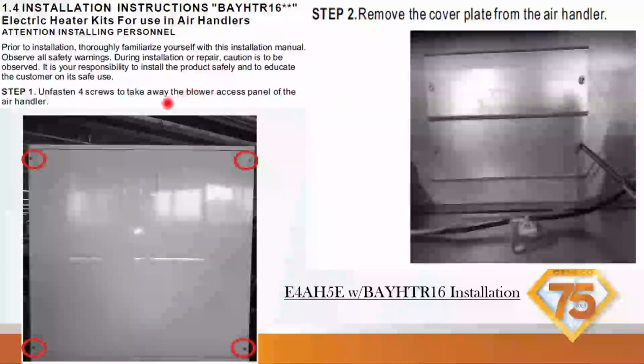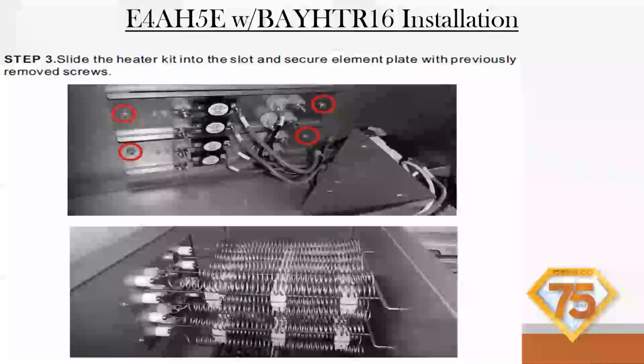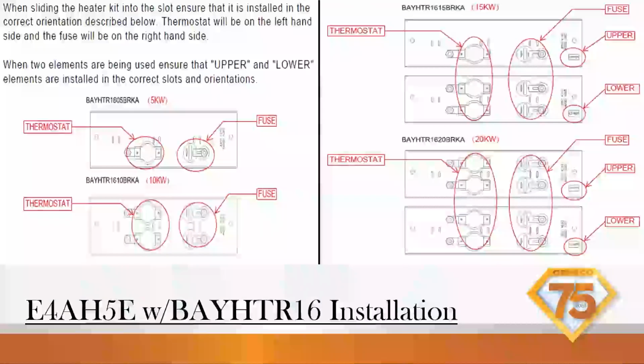Unfasten the 4 screws. Take away the blower access panel of the air handler. So remove the door panel. As you can see, this is a 20 kW. So we have an upper and a bottom, and they are going to have these labels. Slide the heater kit into the slot and secure it with the previously removed screws. You guys are probably used to those. You're going to have to line those up. They do line up pretty good sometimes. Well, most of the time. I have had a few heat strips where they didn't line up. I'd have to pre-drill my own holes. But I was trying to make something work at that point in time, so it wasn't the OEM heat strip kit for that.